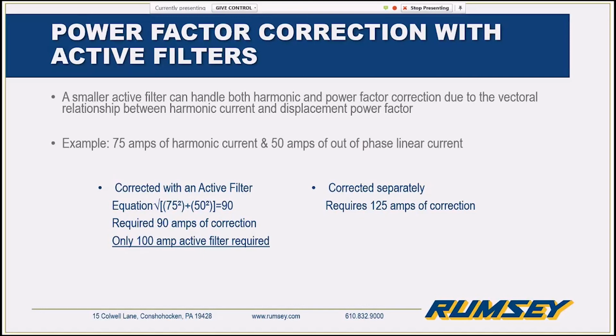But because of the square root of the sum of the squares, when you put those together, you'll see it's only 90 amps of correction that are required. So you got a 100 amp filter. Wouldn't be much of a cost savings in this small example, but you can see how it could add up over the course of a whole facility if we're being put at the switchgear.